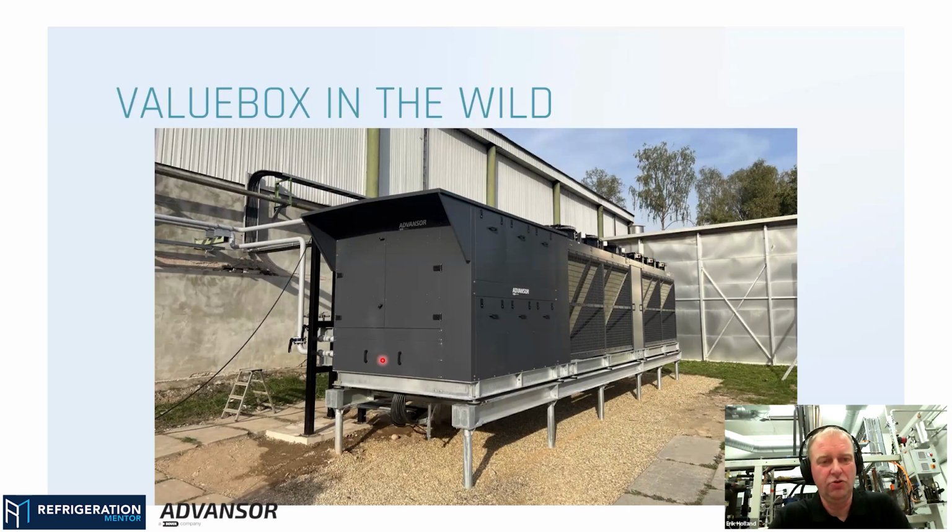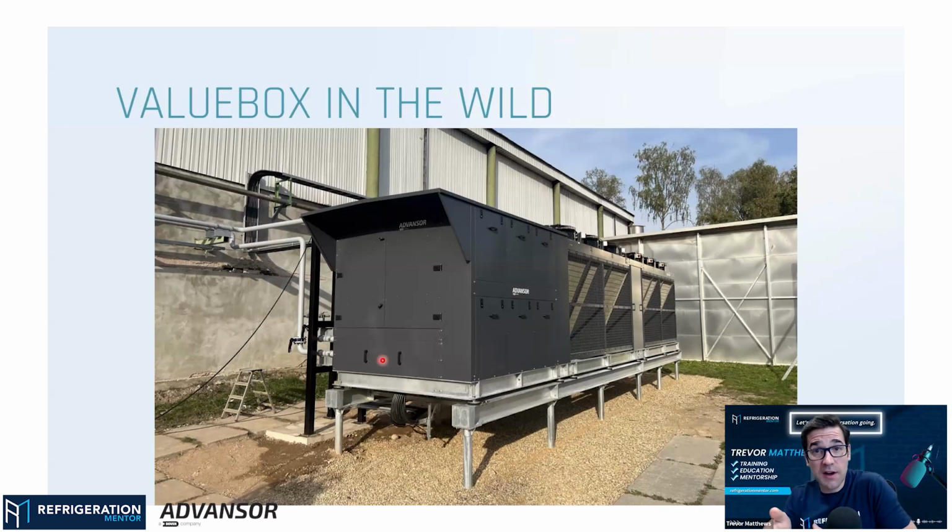Oh, it's super easy work because you have everything set up anyways. You have your vacuum pumps on the system anyways. You have pulled it down to a full vacuum. So now it's just a matter of connecting your oil hose to your oil bucket and opening the valve, and then letting time happen, and it's just going to suck everything in. You don't have to lift a finger or anything. Just have to monitor the levels. And that's huge, because that saves time. And plus, you're still pulling the vacuum, because if you break the vacuum or you add 150 psi or 10 bar of CO2 and then add it, well, then you still have to pull a vacuum again.